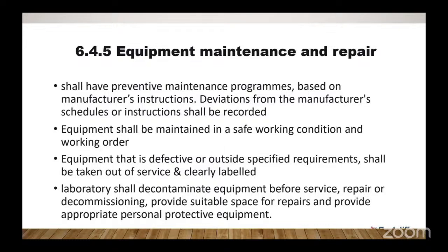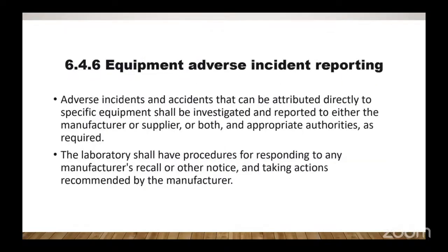The agent you are using to decontaminate it should be stated there. And the record that shows that decontamination was done has to be there. This is very, very crucial to equipment management.